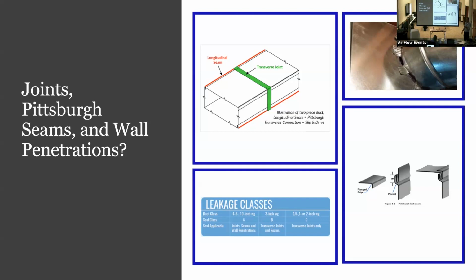So when we put those two pieces together, that Pittsburgh seam, like I showed you before, there's a full-on Pittsburgh seam. This doesn't need to get sealed for low pressure ductwork. Some contractors actually do seal it, some don't. There's no inspection process for this. Maybe if an owner and a contractor have a good relationship, they say, hey, I want all my low pressure ductwork sealed, maybe they don't.